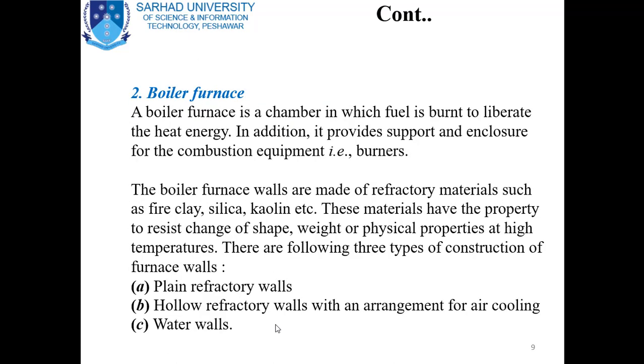The boiler furnace is a chamber in which fuel is burnt to liberate heat energy. In addition, it provides support and enclosure for the combustion equipment — that is, the burners. The boiler furnace walls are made of refractory materials such as fire clay, silica, and kaolin. These materials have the property to resist change of shape, weight, and physical properties at high temperatures.